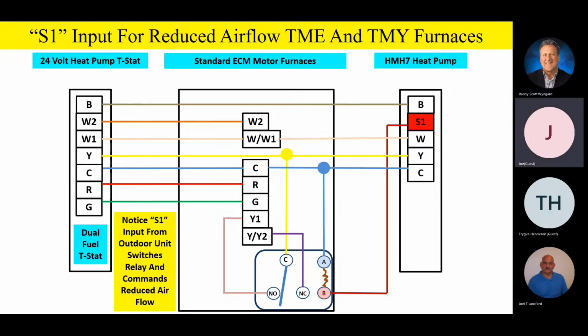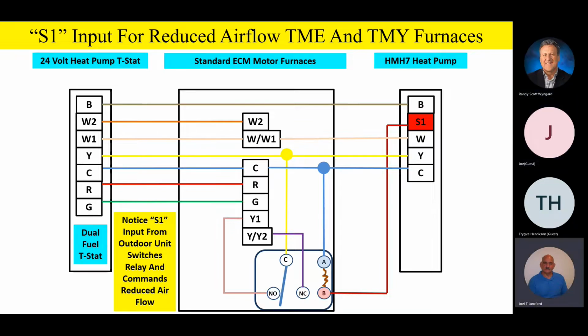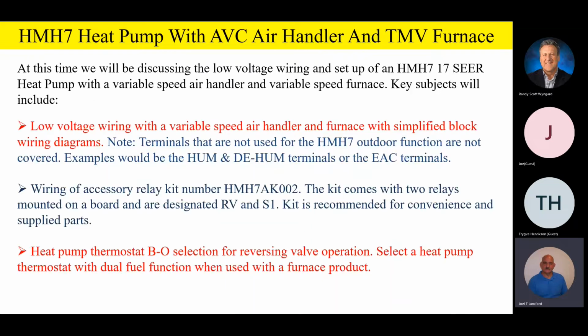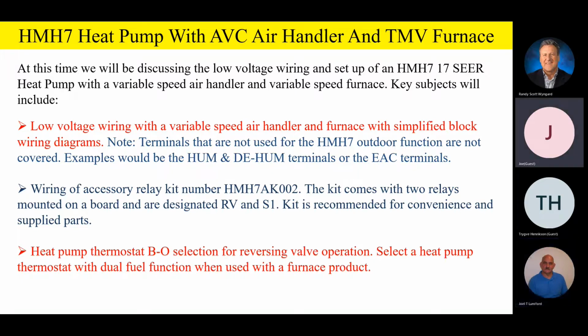Thank you. Okay, fellas, let's go ahead and take a look at this time. We're going to be discussing low voltage wiring and setup with a variable speed air handler and a variable speed furnace. Now, it should be noted that for the low voltage wiring with the variable speed air handler and furnace, we're going to use a simplified block wiring diagram like we had before, and there will be terminals that are not used for the HMH7 outdoor function are not covered.